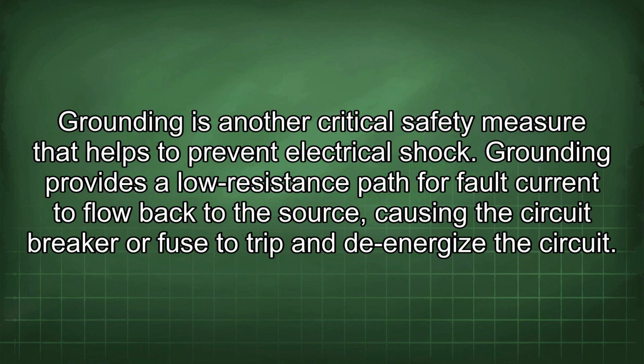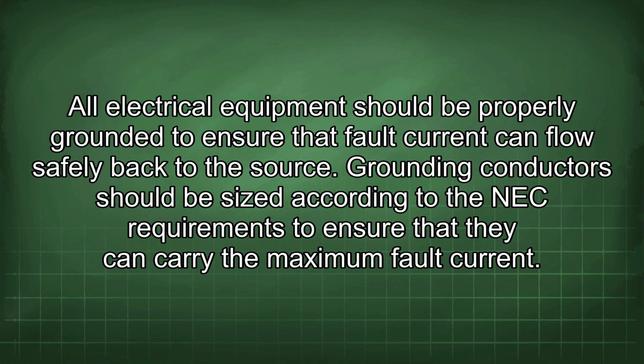Grounding is another critical safety measure that helps to prevent electrical shock. Grounding provides a low-resistance path for fault current to flow back to the source, causing the circuit breaker or fuse to trip and de-energize the circuit. All electrical equipment should be properly grounded to ensure that fault current can flow safely back to the source. Grounding conductors should be sized according to the NEC requirements to ensure that they can carry the maximum fault current.